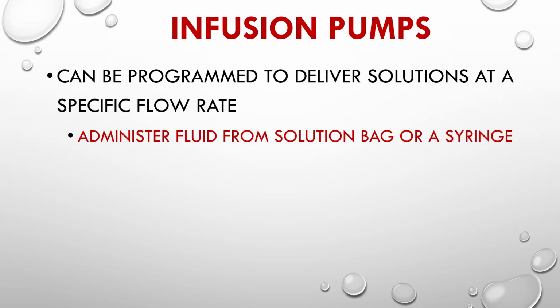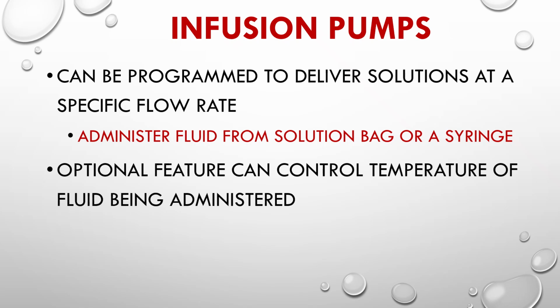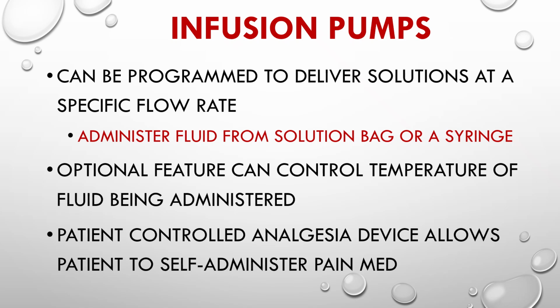Our infusion pumps, so these can be programmed to deliver solutions at a specific flow rate. So these would be hooked up to an IV bag. They administer the fluid from the solution bag or syringe to the patient. Optional features can control temperature of the fluid in addition to the flow rate.